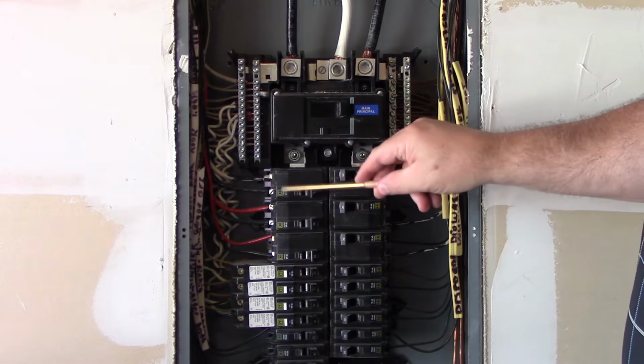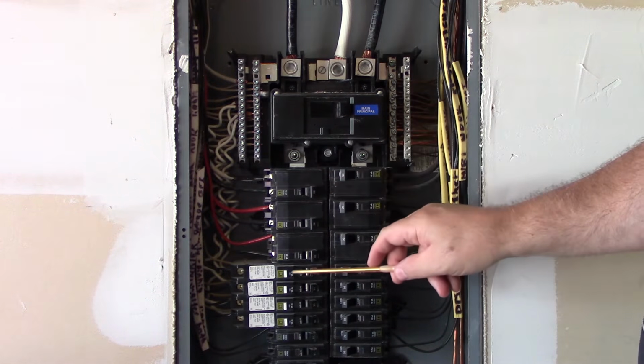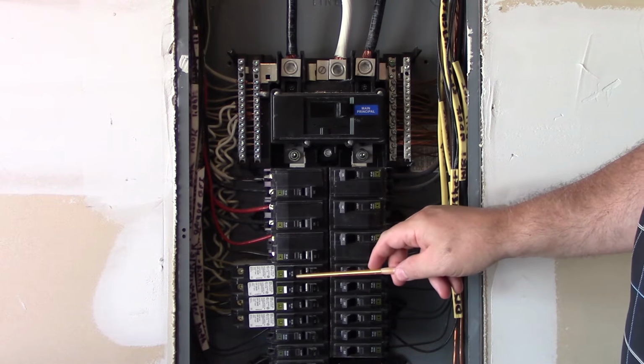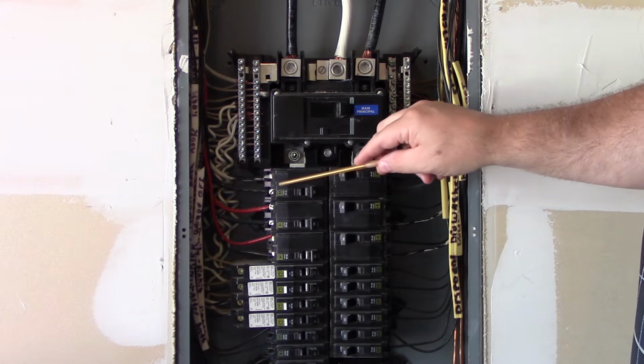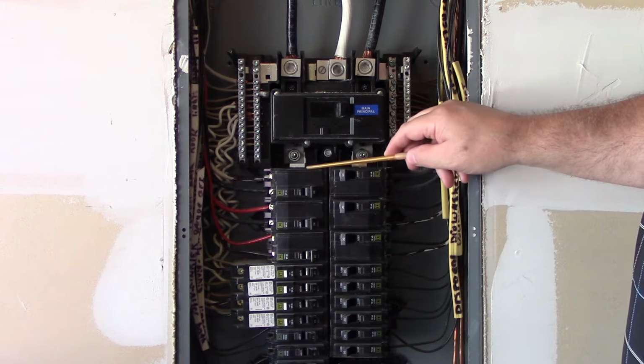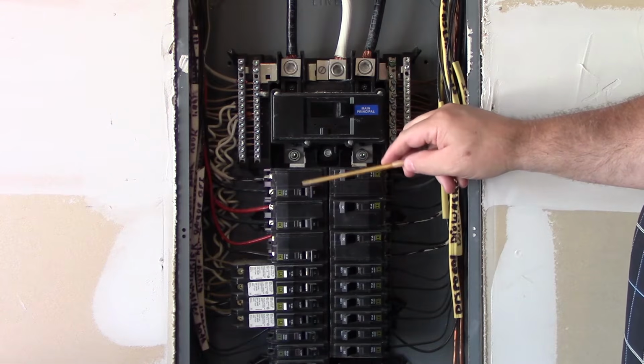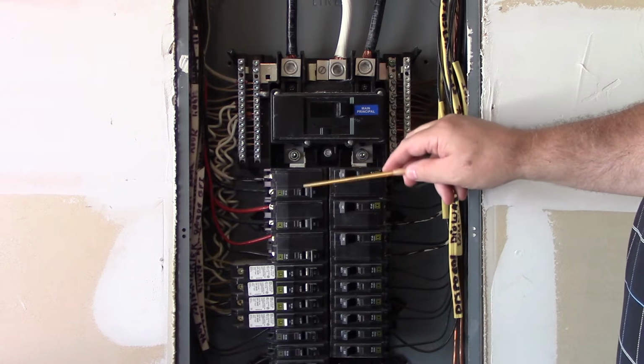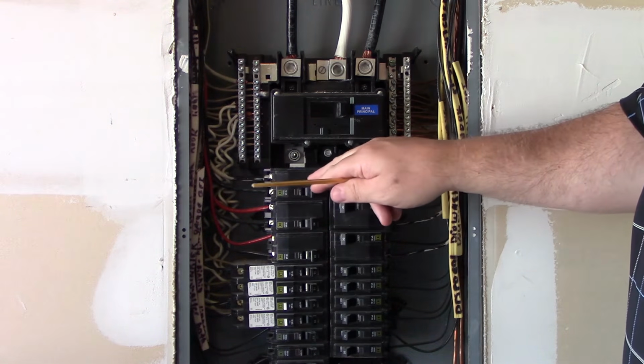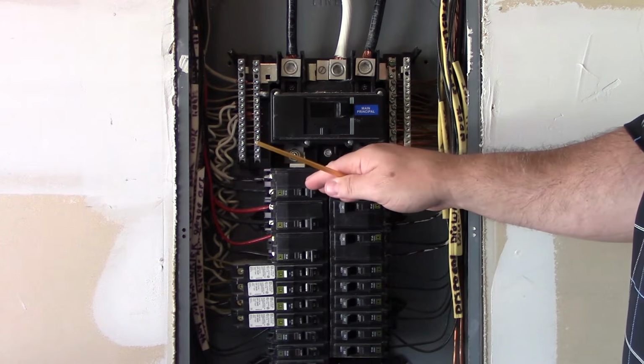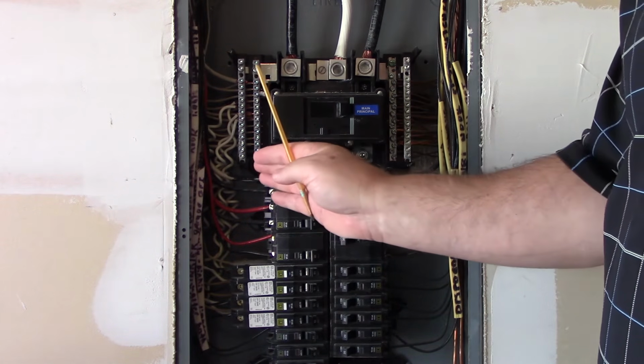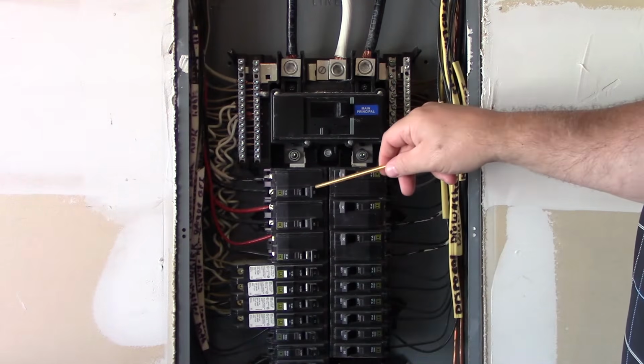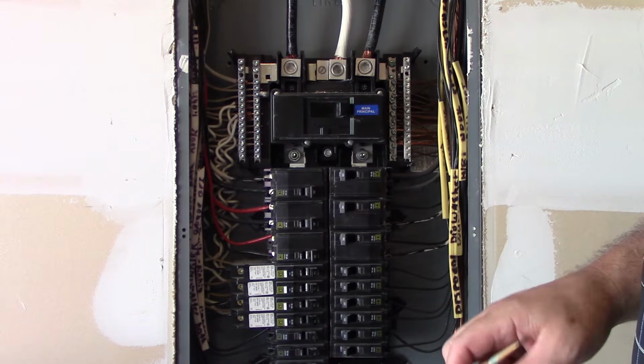All right, again, these are considered two-pole breakers. These are considered single-pole breakers. This happens to be Square D, which tends to have one lever on a two-pole, whereas some of them you might see two levers, and they have what's called an identified handle tie. It is listed to use with that breaker. It's identified for its application, and it can turn off both of the toggles on the breaker itself.